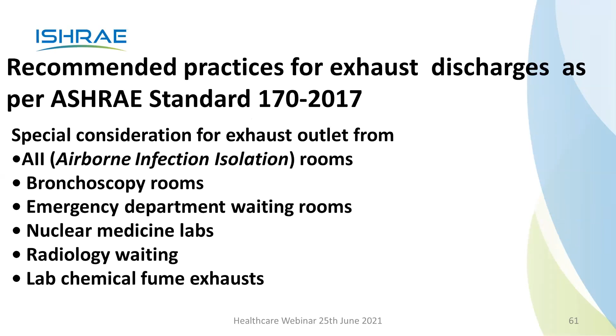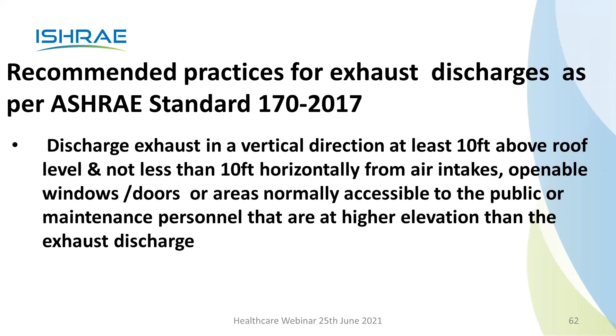Discharge the exhaust in a vertical direction at least 10 feet above the roof level and not less than 10 feet horizontally from air intakes, openable windows, doors, and areas normally accessible to the public or maintenance personnel that are at a higher elevation than the exhaust discharge. Discharges should be located in such a way that they minimize the recirculation of the exhausted air back into the building.